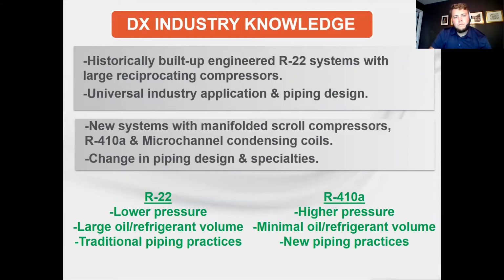So today we're using more scroll compressors due to efficiency. The new systems have manifolded scroll compressors. They have used R410A for the past 10 years. And recently, microchannel condenser coils have taken over because of the reduced volume of refrigerant that they use. So this has made a lot of changes in some of the rules that we followed with R22. The pressures are higher, the refrigerant volume is less. Oil and refrigerant management is much more critical than it used to be.